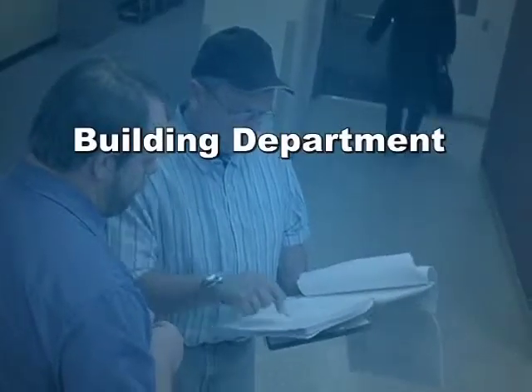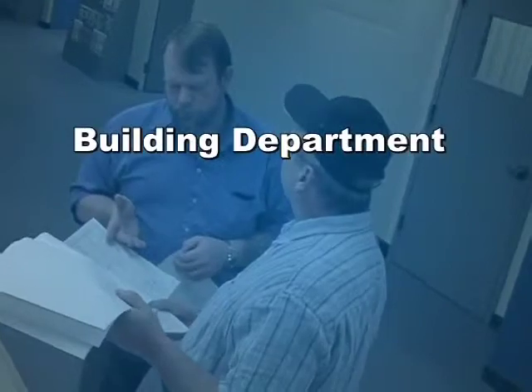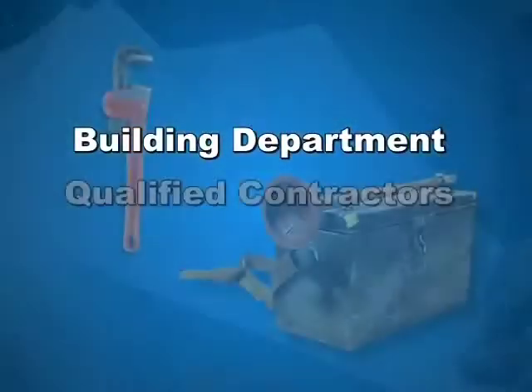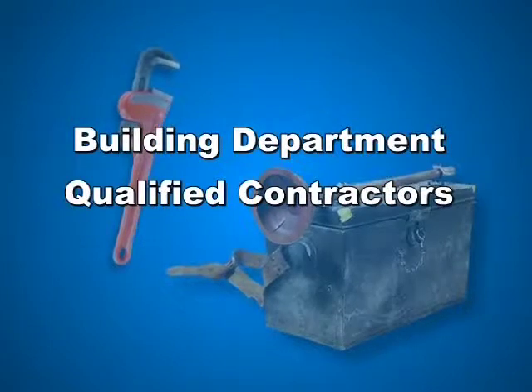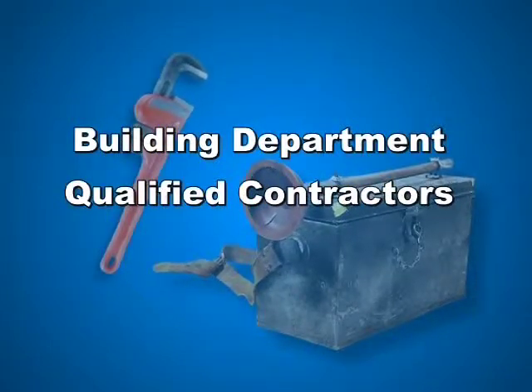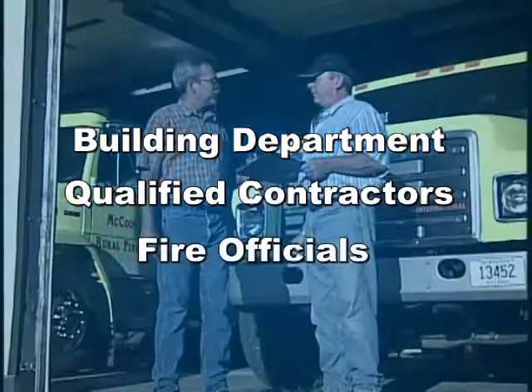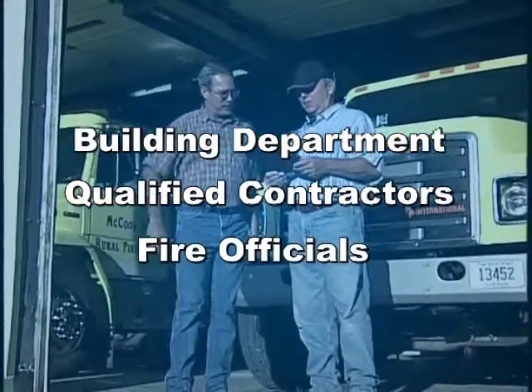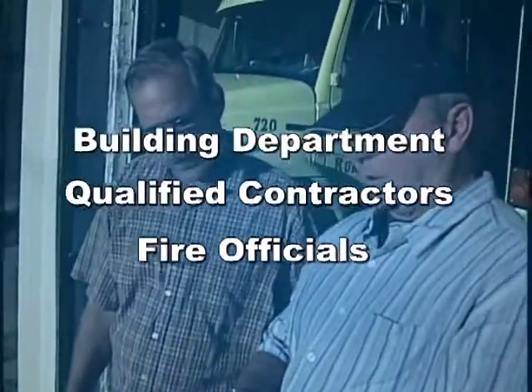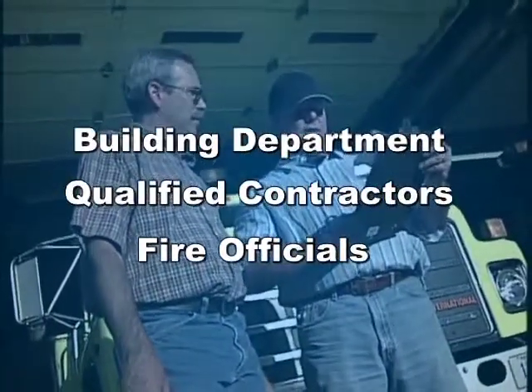Working with other agencies can be a big benefit to your cross-connection control program. Be sure to touch base with your local building department to get included in their plan review process so backflow preventers can be included in the planning stage. Local plumbers can serve as extra eyes to catch problems with building plans that might create a need for backflow prevention. Working with fire officials is also very important. The installation of backflow preventers on fire sprinkler systems will decrease the water pressure, and this needs to be considered in the water system design. Working closely with these officials and individuals will solve problems before they become problems and will be sure to generate some good PR for you.